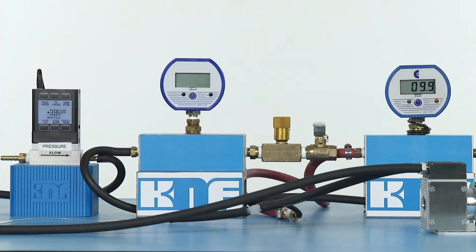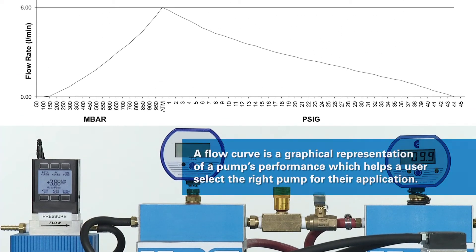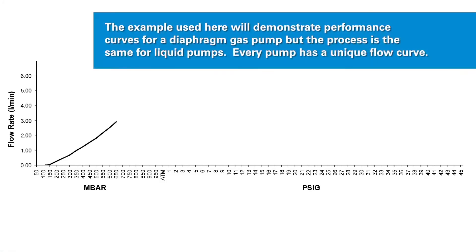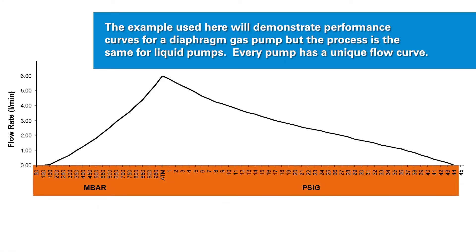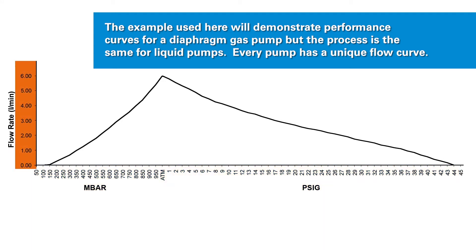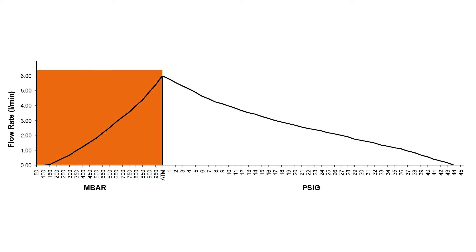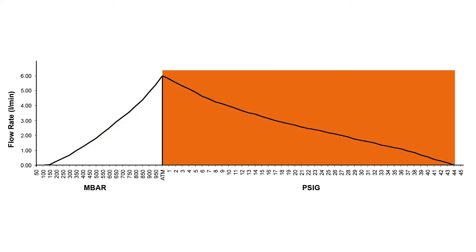For every vacuum pump and compressor that KNF manufactures, a flow curve is generated to illustrate the expected performance capabilities across the rated pressure range. The performance is mapped on a chart where the x-axis is pressure and the y-axis is flow rate. The center line represents atmospheric pressure, so that the left half of the curve displays vacuum, measured in millibar absolute or inches mercury, and the right half represents pressure, measured in PSIG or bar G.